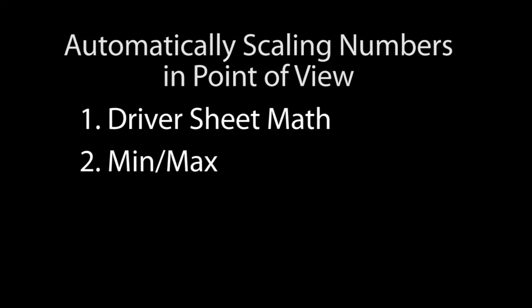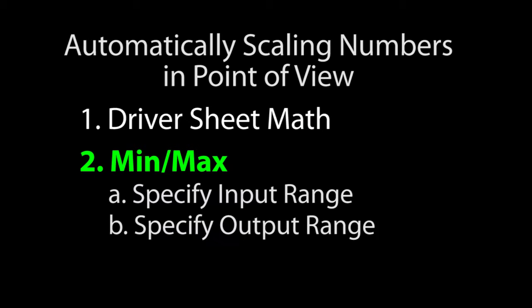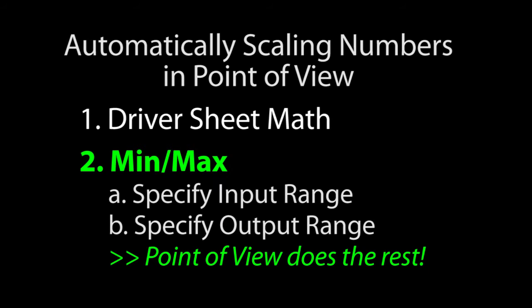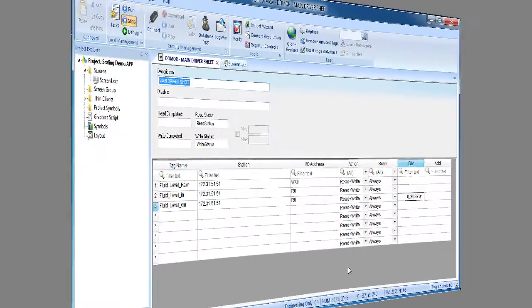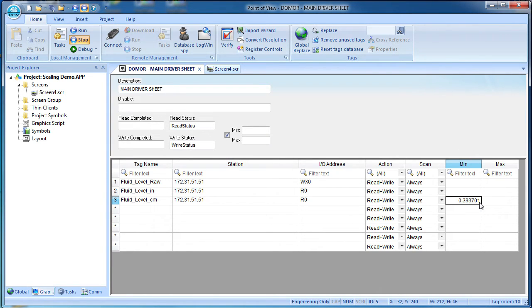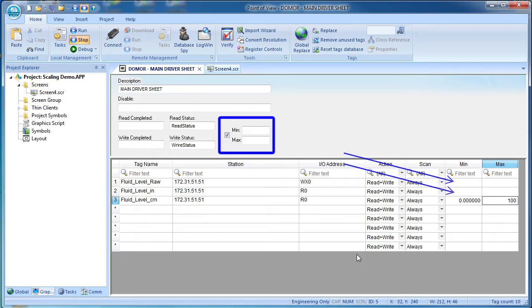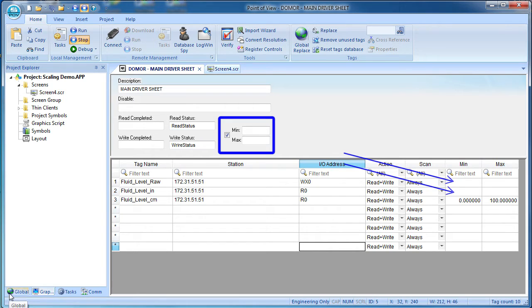The second method is the min max method. You specify the min max of the incoming data and the min and the max that you want the local Point of View tag to have. And Point of View automatically does the magic to make it happen. To use this method, go to the driver sheet and click on this min max check box. That changes these columns to min and max. So now we put the incoming tags actual min and max here which in our example is 0 to 100 inches. We can also put a global min and max here which serves as the default for all rows if min and max aren't overridden on that row. I'll leave those blanks so the values are just brought in as is. Save that.